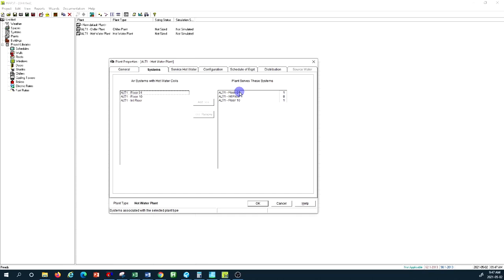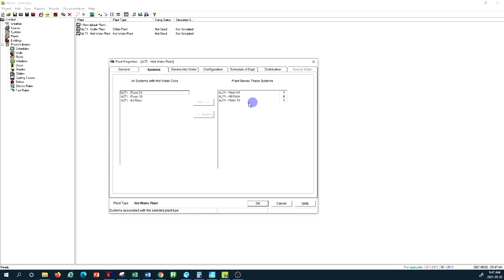All air systems with hot water coils are part of this load. For service hot water, we have nothing because this is not a service hot water boiler system. For configuration, I keep two equally-sized boilers. For plant control, I set equal unloading with reset by return water temperature. The design hot water setpoint I change to 150°F — suitable for condensing boilers — with 130°F as minimum, maintaining a 20-degree delta T.